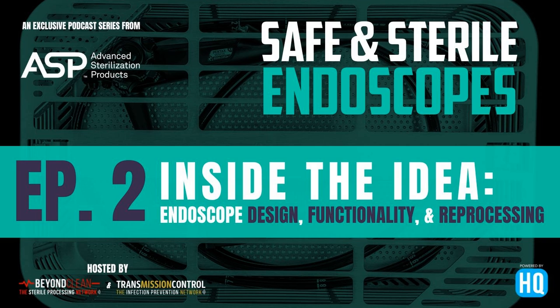And we're certainly not going to tell anybody that you can't high level disinfect. That's going to be facility by facility for their preference. But again, you've got to think about what that is doing to the scope. Well, now we're high level disinfecting and we're going to sterilize each of these scopes. But we also know that they're already sending them down for ethylene oxide, which is very, very harsh on the scopes. So they're already used to ERCP scopes either going out for repair a lot sooner or going out for that surveillance to make sure that everything's still intact. So they're going to already be used to that from an ETO perspective. Now just shifting over to low temp, I think they'll see that extended out a few more cycles than what the ETO recommendation was.